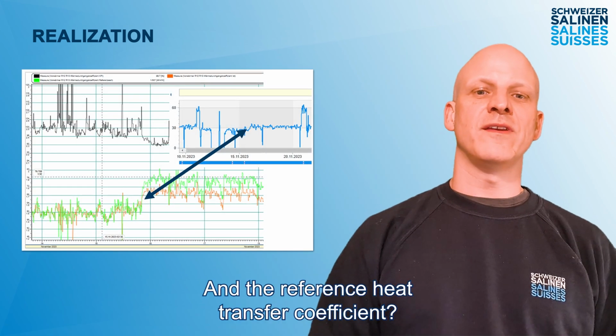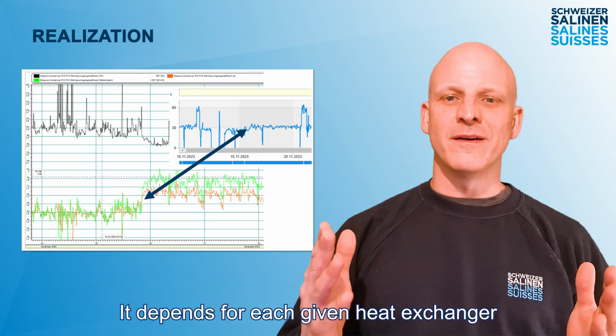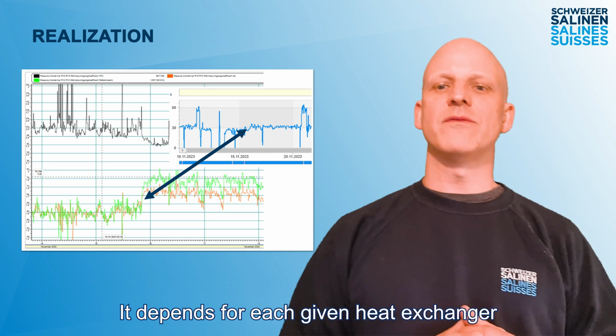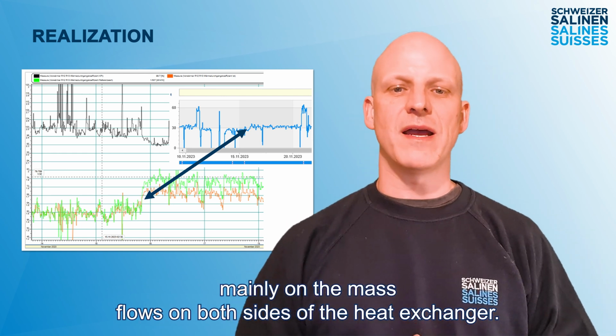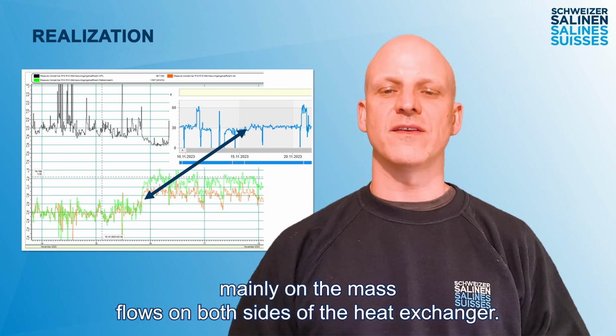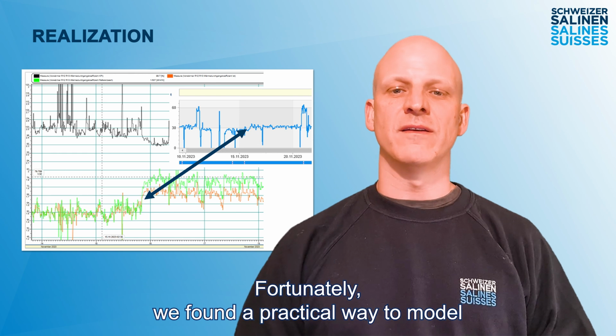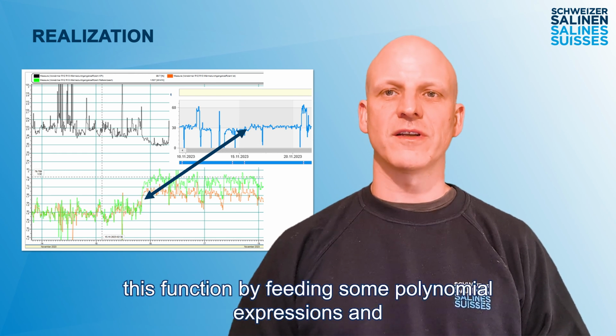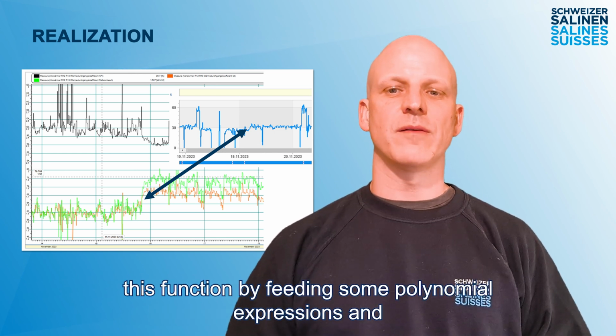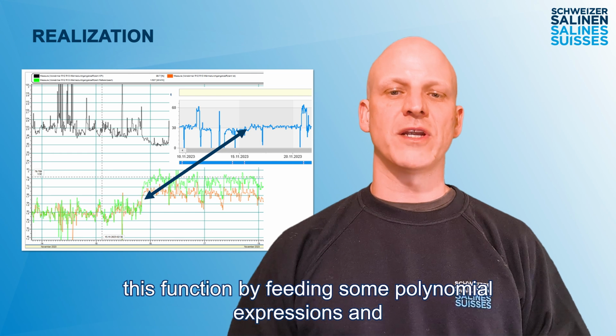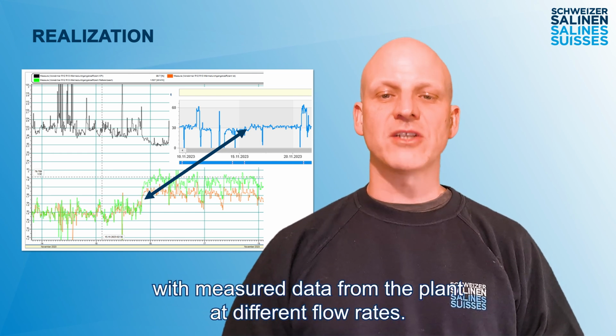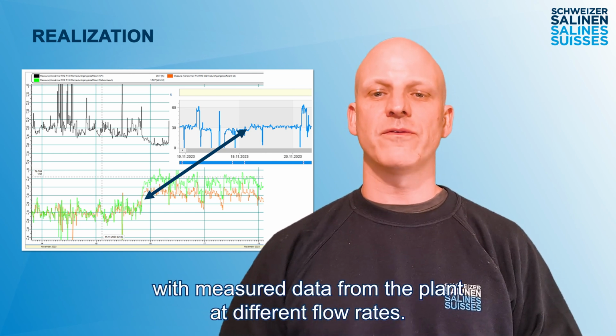And the reference heat transfer coefficient? Well, it depends for each given heat exchanger mainly on the mass flows on both sides of the heat exchanger. Fortunately, we found a practical way to model this function by feeding some polynomial expressions and equations with measured data from the plant at different flow rates.